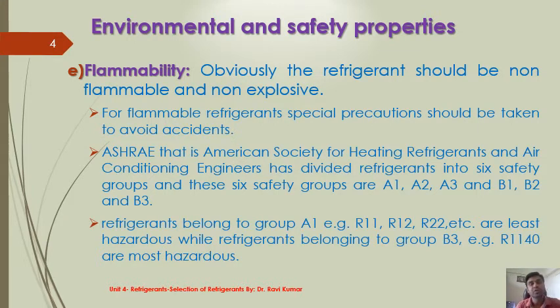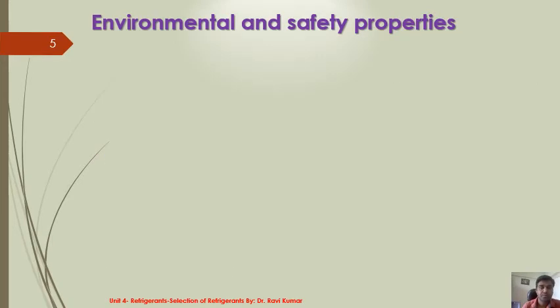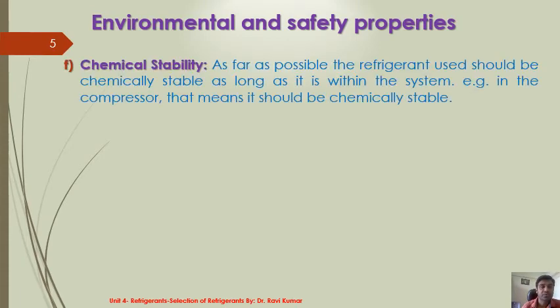The refrigerants belonging to group A1, such as R12 and R22, are the least hazardous, while the refrigerants belonging to group B3, for example R1140, are the most hazardous refrigerants. The next property is chemical stability. As far as possible, the refrigerant should be chemically stable as long as it is within the system — for example in the compressor — meaning it should be chemically stable for a long time.